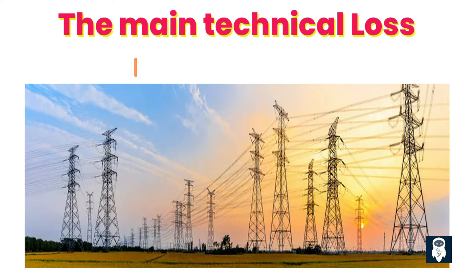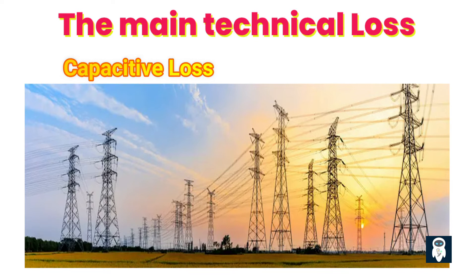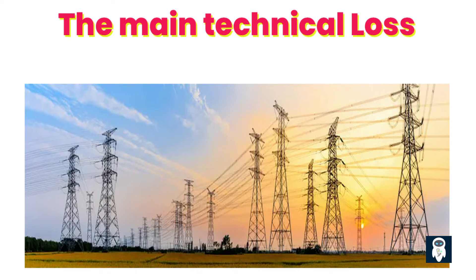Balancing the reactive power in the network through proper capacitor placement and utilizing more efficient equipment helps reduce inductive losses. Capacitive losses occur when excess reactive power is generated in the power system, which can lead to over-voltage conditions and energy losses due to the reactive power flowing back and forth. Reactive power compensation techniques, like installing shunt capacitors, help minimize these losses.